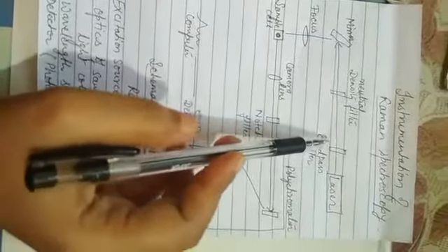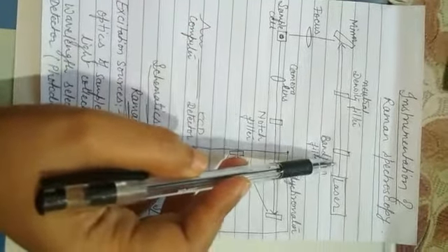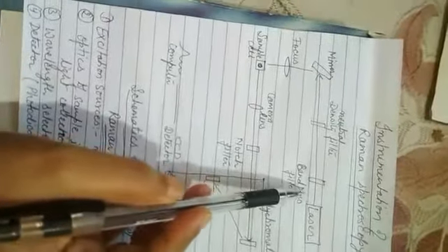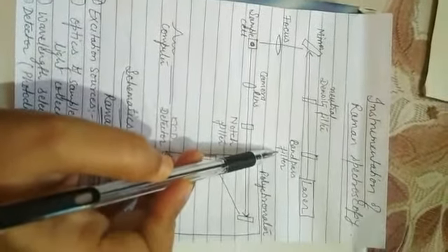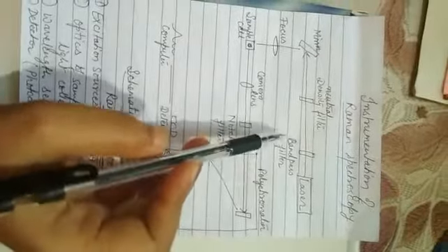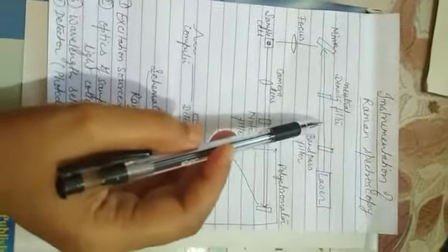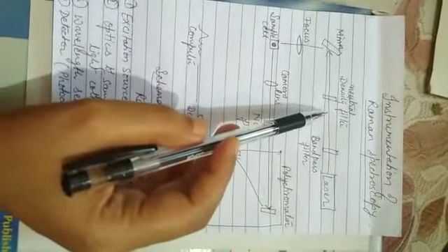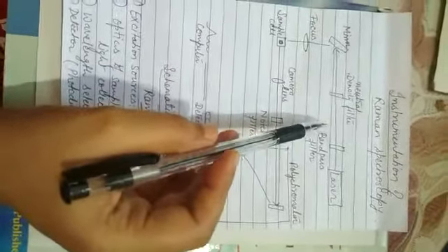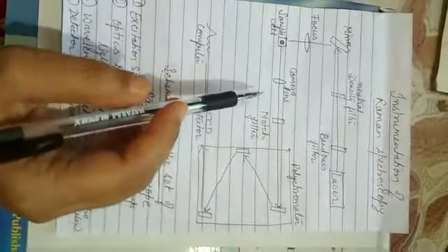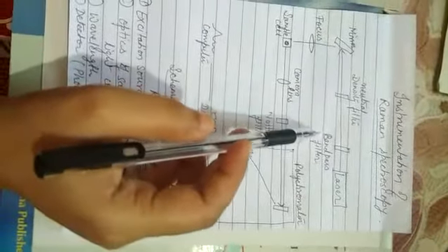A combination of notch filter and high quality grating monochromator is mostly employed in dispersive instrumentation. Double or even triple grating monochromators, super notch filters and rejection filters are used to separate relatively weak Raman lines from intense Rayleigh scattering radiation.